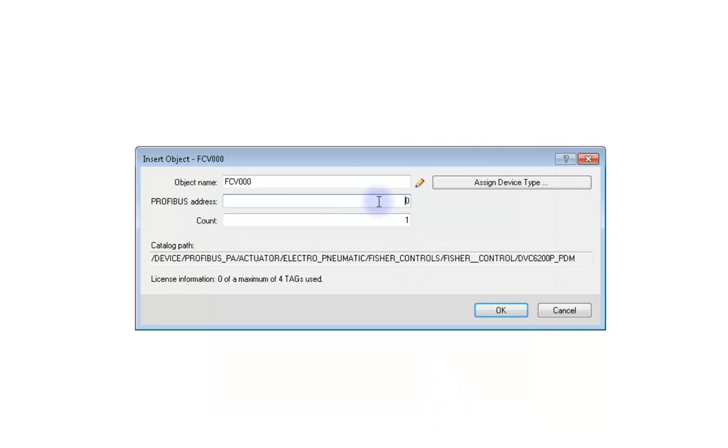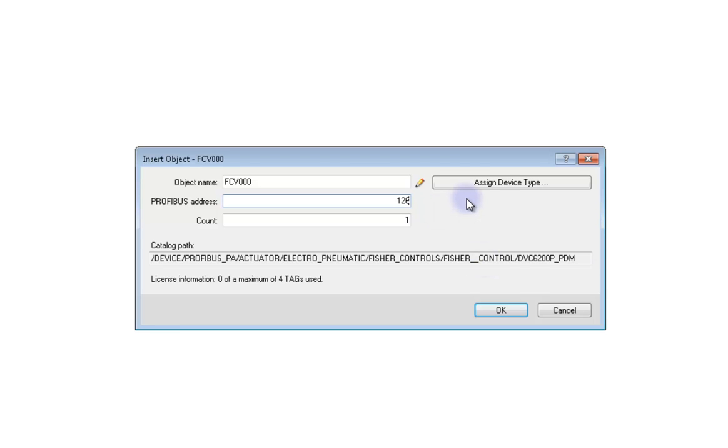Let's change the name of the DVC6200P address to 126 which is the default. It could be something different so make sure that you've double checked and know for sure. The setup won't work otherwise. Click OK to continue.